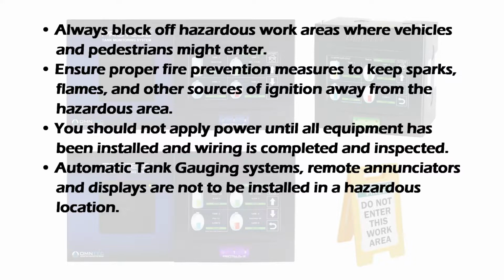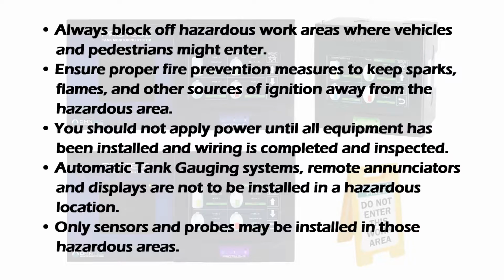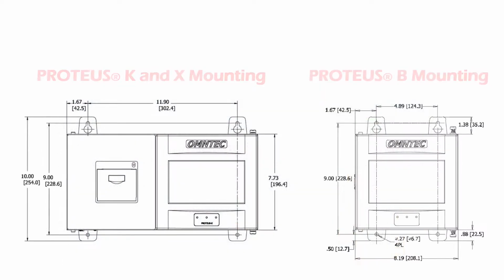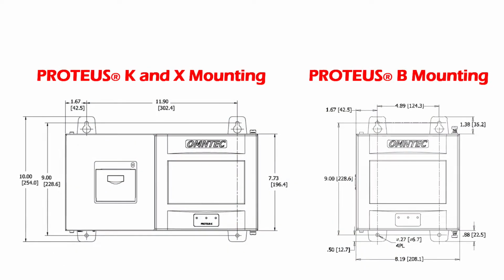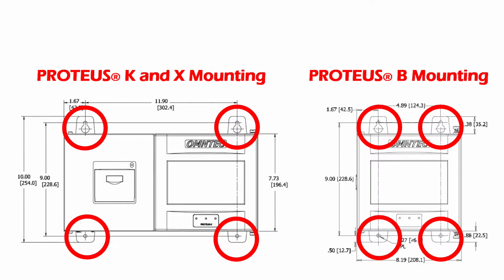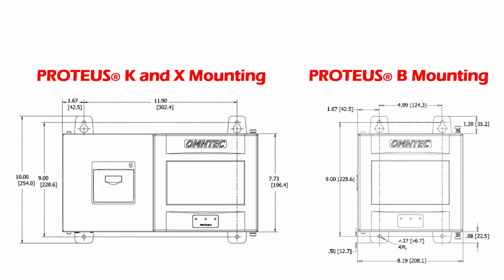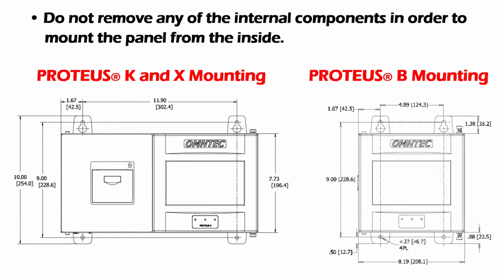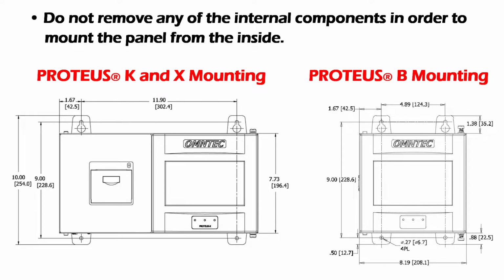Automatic tank gauging systems, remote annunciators, and displays are not to be installed in a hazardous location. Only sensors and probes may be installed in those hazardous areas. The controller is mounted on the wall, using the mounting flanges and the proper anchors and bolts for the wall type. Do not remove any of the internal components in order to mount the panel from the inside.